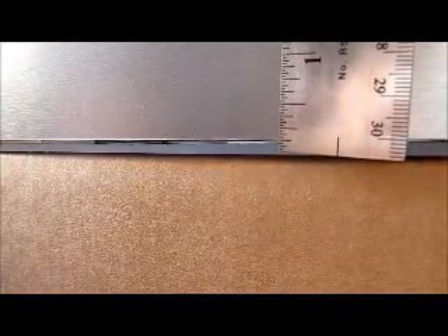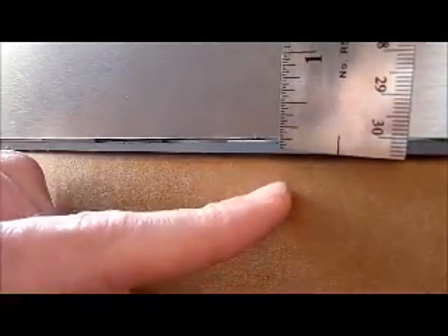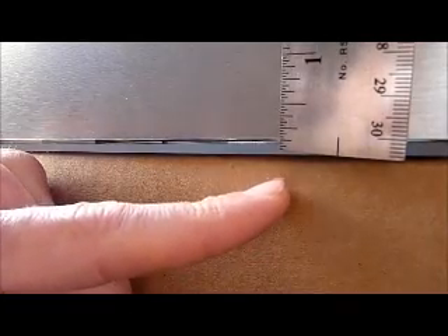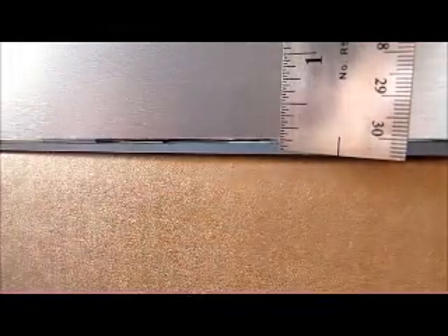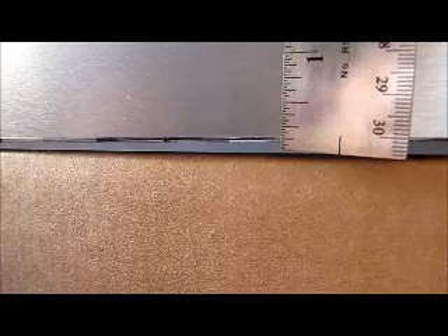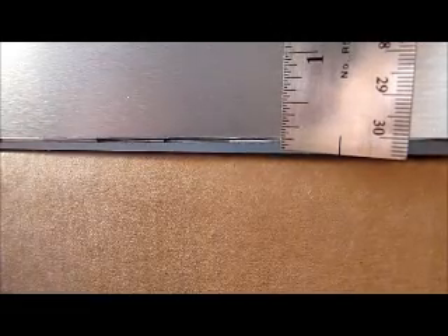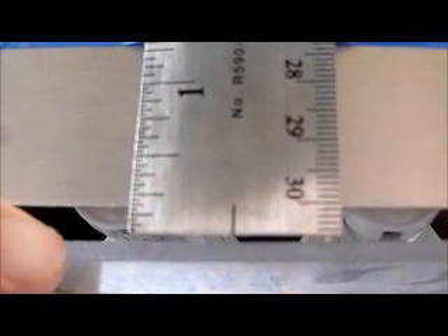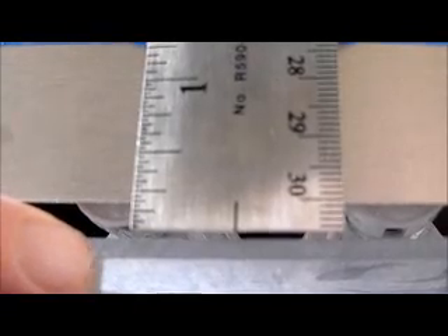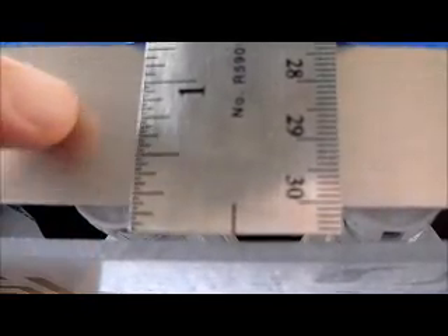For the purposes of this illustration, we've placed a box underneath the acrylic shield to push it upwards to reduce this gap to 1/8 inch. Typically, that's not enough to allow enough hot air to exit the fixture and allow the fixture to cool properly. Here's what it should look like. Again, approximately 1/4 inch between the acrylic shield and the side of the housing.